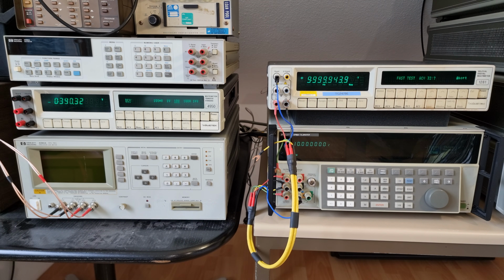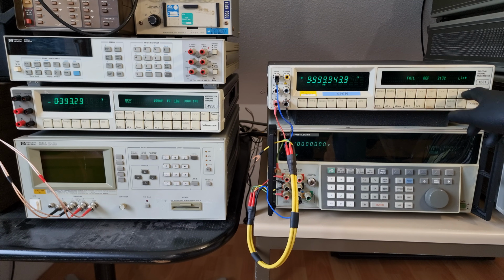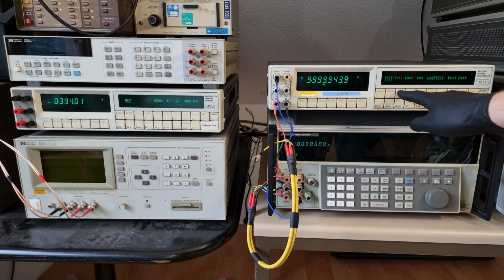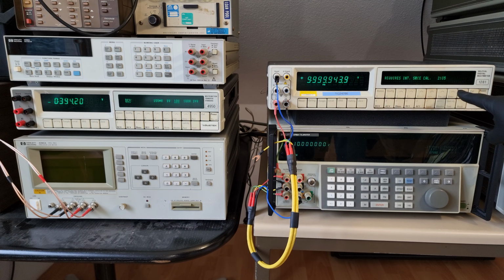A fast self-test reveals a reference error 2132, which the publicly available documentation translates to an internal reference 2 being outside of an allowed voltage range. So there are two LTZ1000 modules in here, and number 2 seems to have a wrong voltage. How unusual. A full self-test is cheekily refused to us with similar reasoning. It wants to calibrate its internal sources first. That's routinely done only after performing external adjustments.